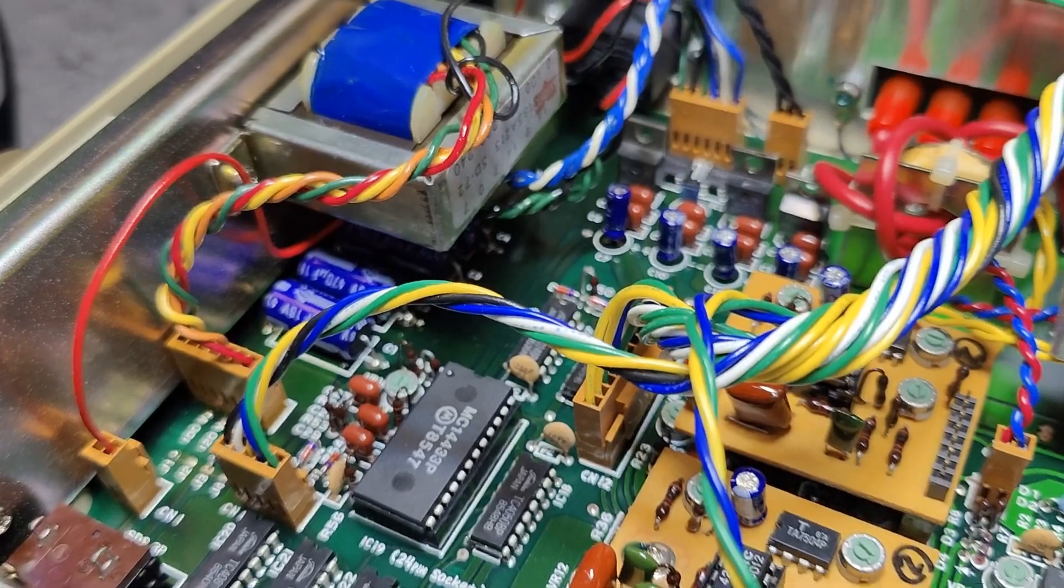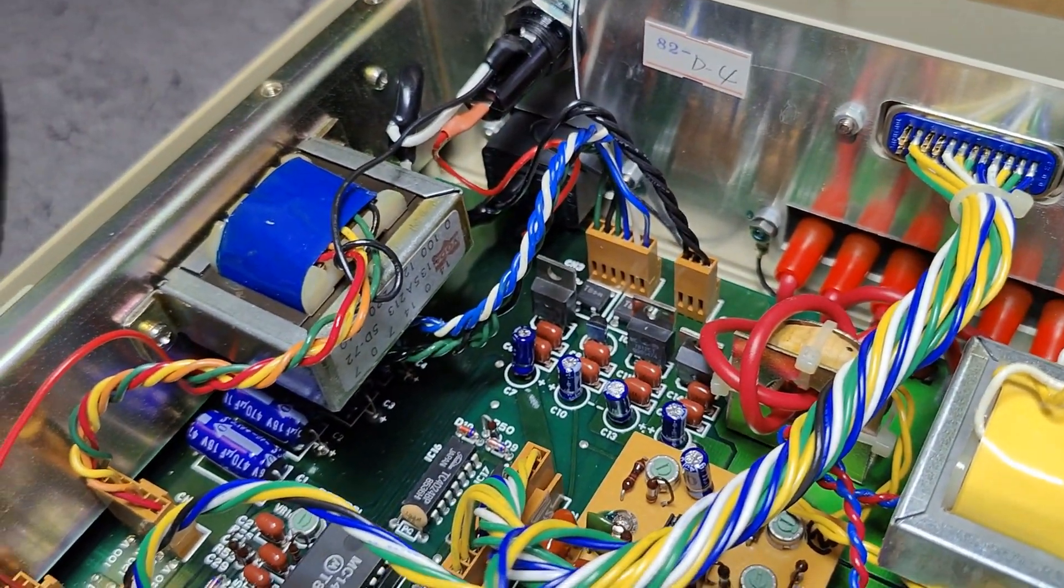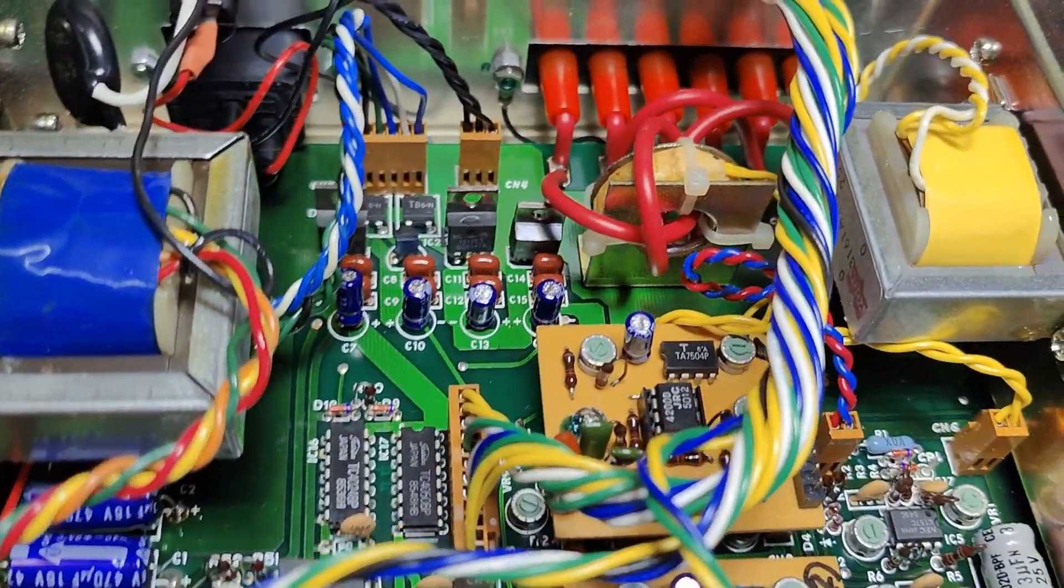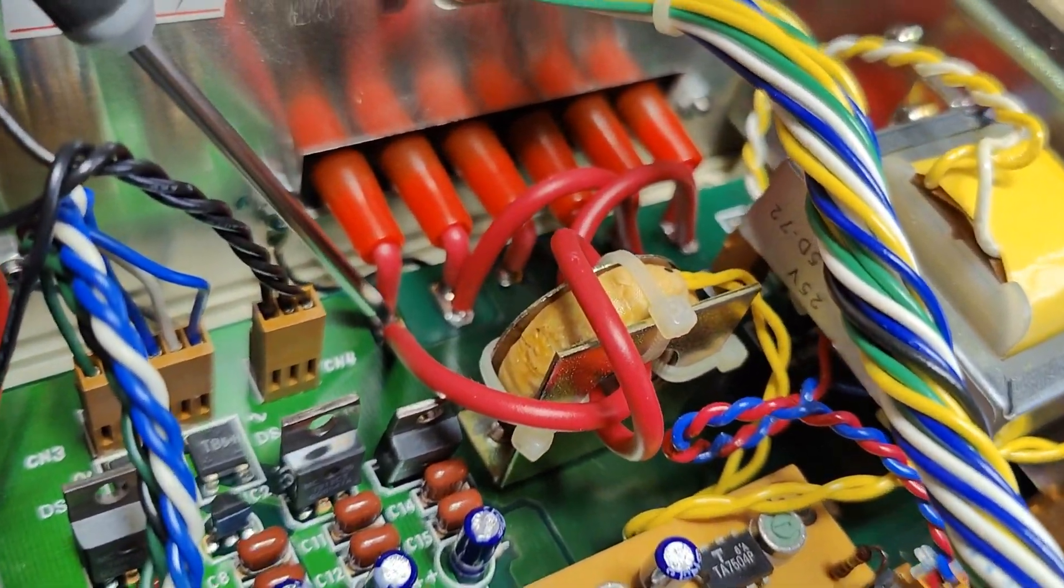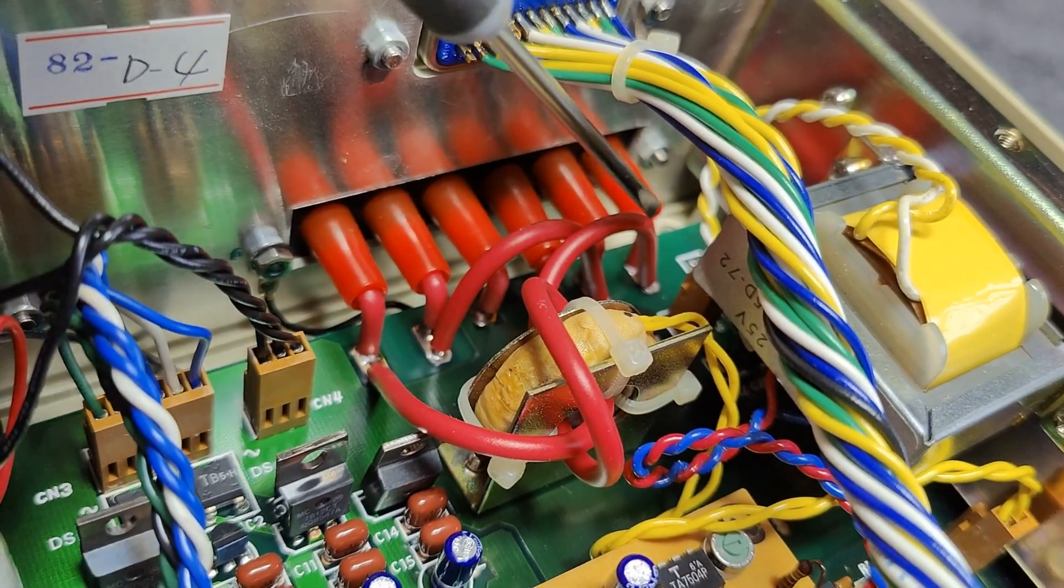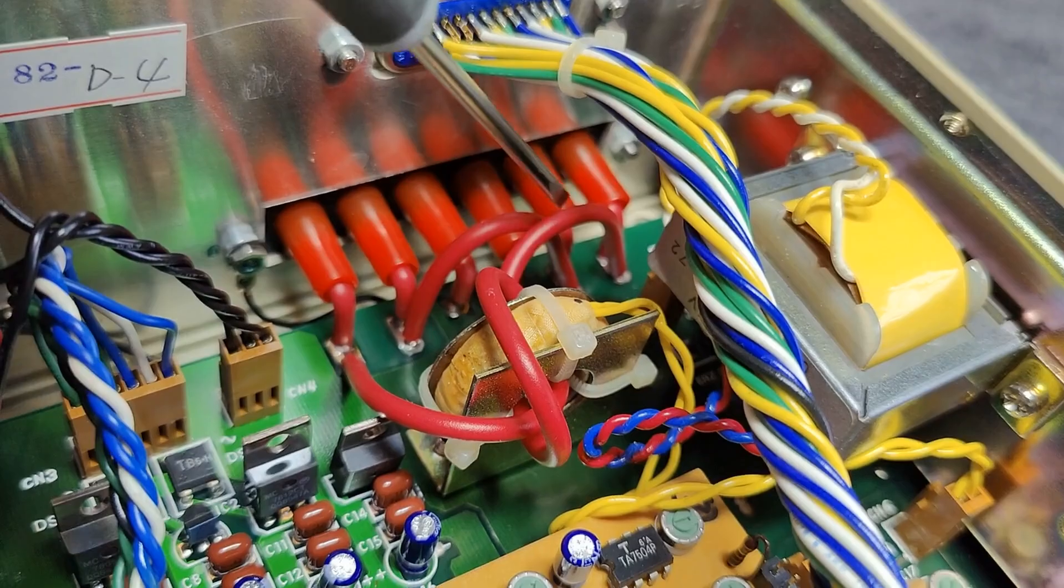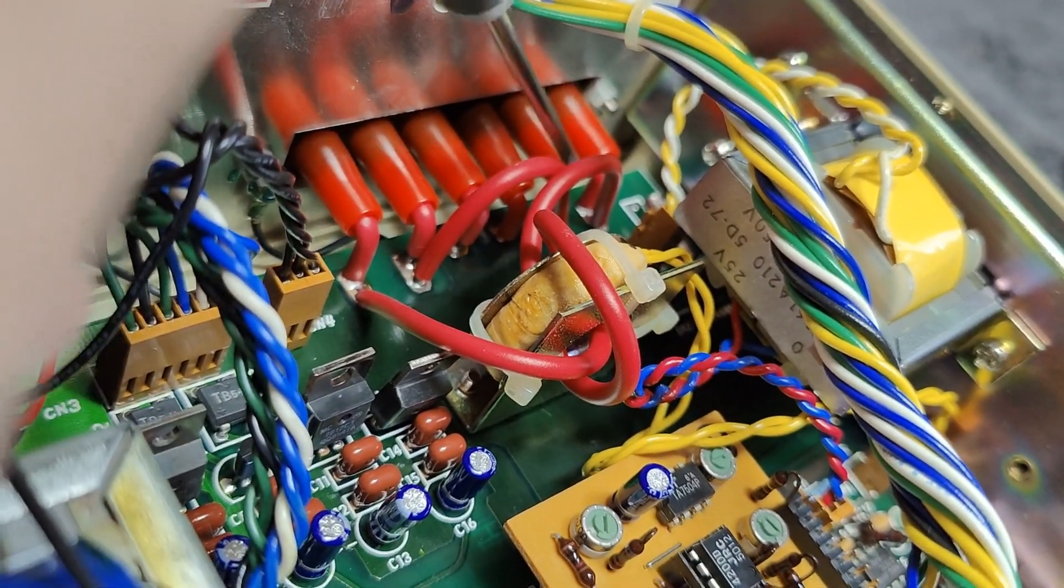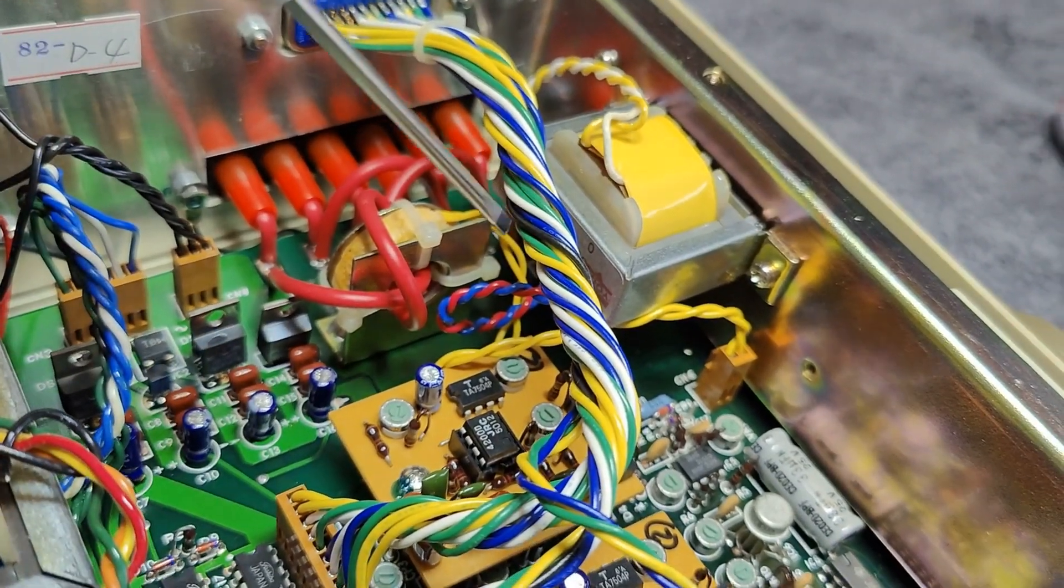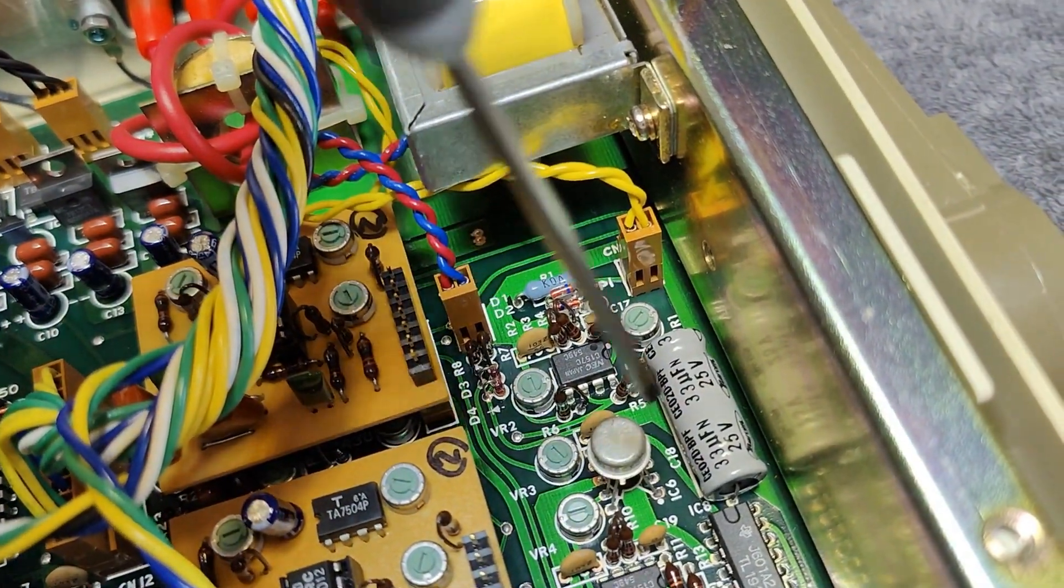The first thing I check for is all the capacitors here for leaks and all that. Perfectly fine, we don't have any leaks. That would be the current transformer. We've got two windings through here, and it shows exactly what we're supposed to see from the manual. We can also see this is the current path, and then here is the voltage from the input to the output. That's just a wire through here. Then we have a wire like that one that is connected to the input voltage and goes to the voltage transformer. The output from the voltage transformer here goes to the little circuit right here.